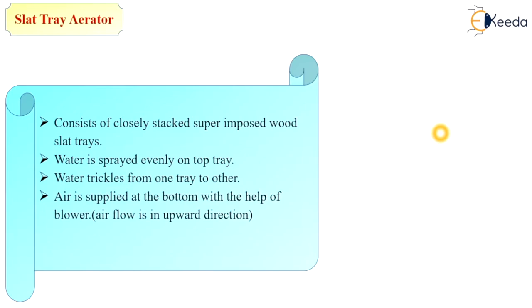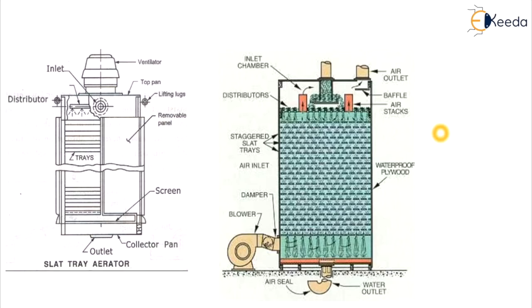The next type is the slat tray aerator. It consists of closely stacked, superimposed wood slat trays and water is sprayed evenly on the top tray, then trickles from one tray to another. There are a number of trays layered one upon another, and air is supplied at the bottom with the help of blowers. Air flows in an upward direction while a ventilator discharges air and gases. Water trickles downward through the trays and the transfer mechanism takes place.